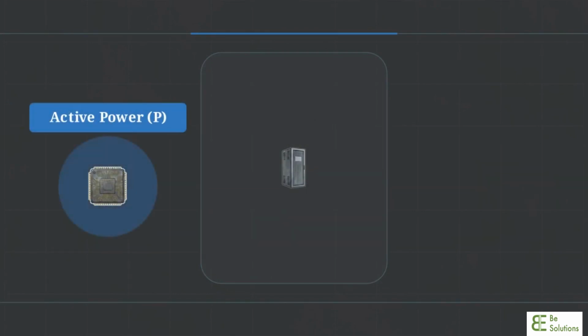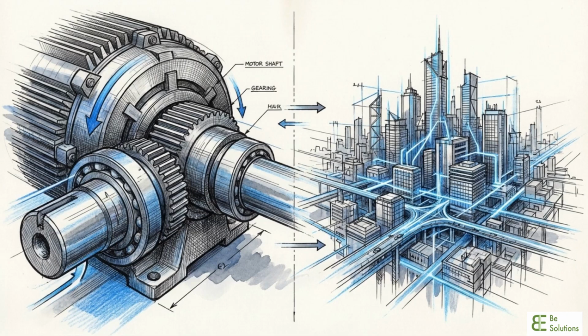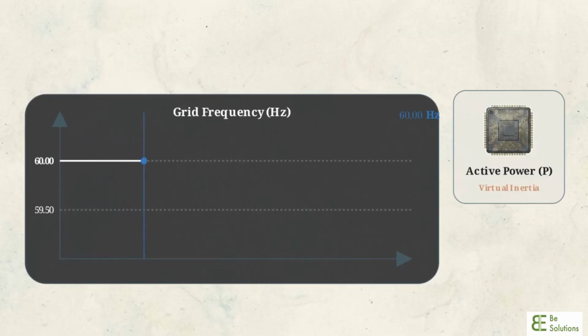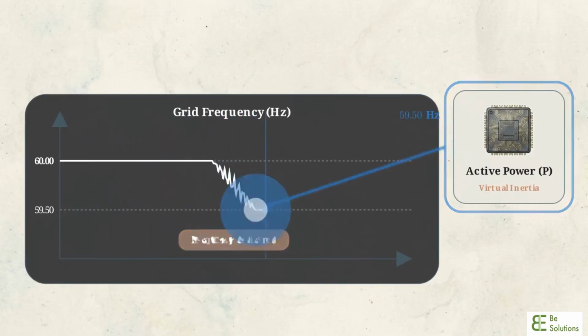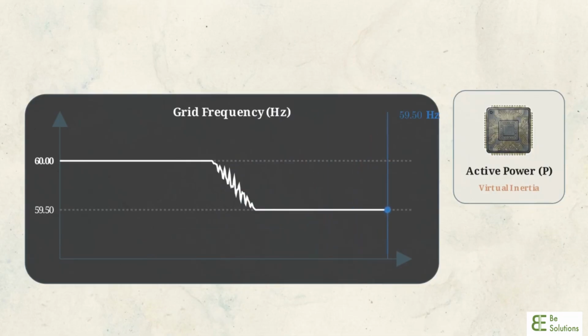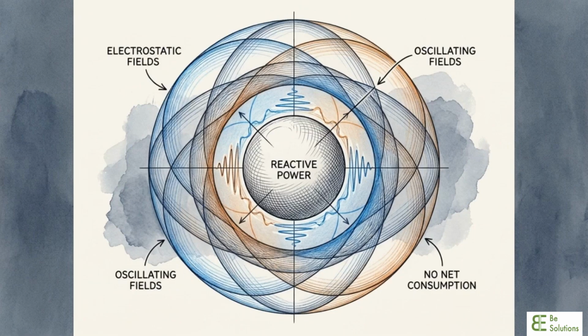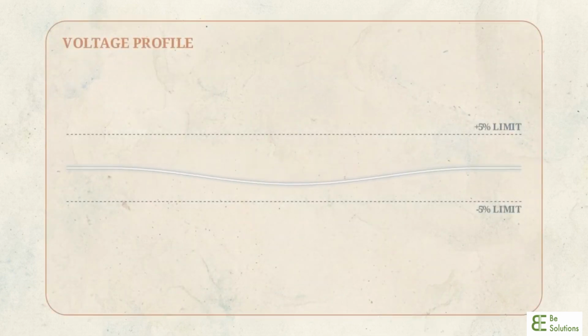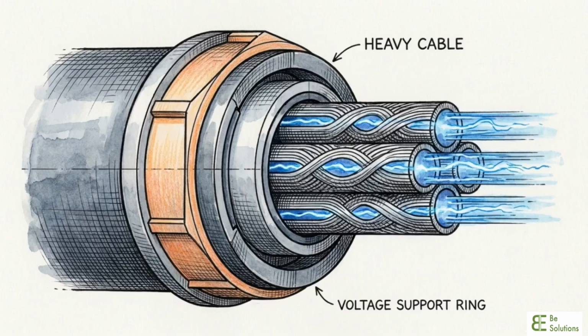That emulation requires two distinct outputs. First is active power. This represents the actual energy transfer that drives physical work, like running industrial motors or lighting a city. Injecting active power provides virtual inertia and rapid frequency containment, arresting rapid drops in the grid's operating frequency. Second is reactive power. This is energy that continuously oscillates between electromagnetic and electrostatic fields without actually being consumed. Its strict purpose is to sustain localized voltage profiles. Without a sufficient baseline of reactive power to support the voltage, active power cannot physically travel across the transmission lines.